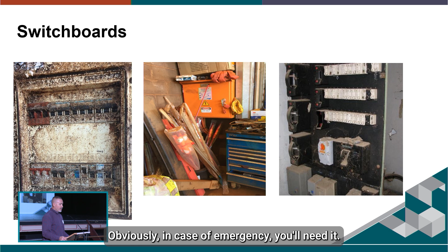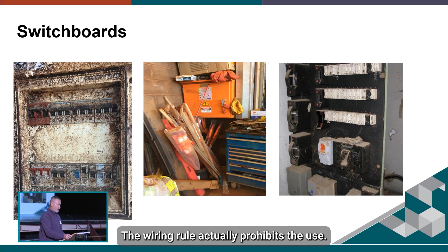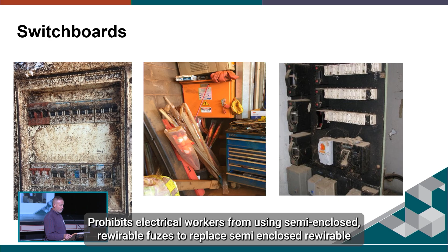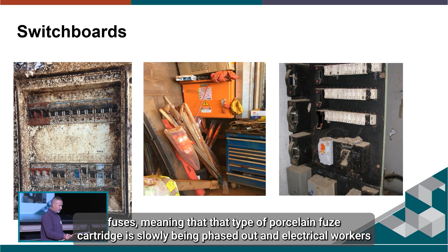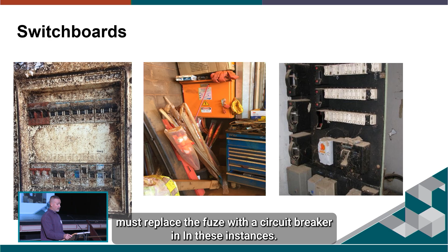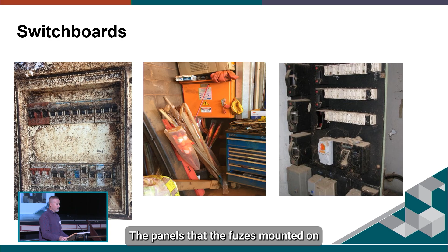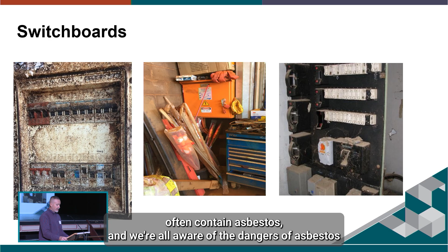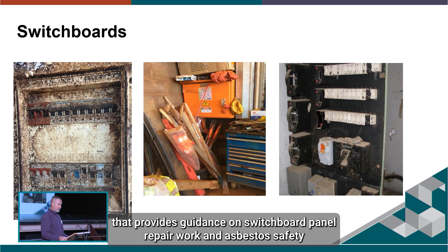On the right-hand side there, you'll see an older type of meter panel, switchboard box with the black background. The wiring rule actually prohibits electrical workers from using semi-enclosed rewirable fuses to replace semi-enclosed rewirable fuses, meaning that type of porcelain fuse cartridge is slowly being phased out, and electrical workers must replace the fuse with a circuit breaker in these instances. The panels that the fuses are mounted on are often asbestos, and we're all aware of the dangers of asbestos. Building and Energy have published a fact sheet that provides guidance on switchboard panel repair work and asbestos safety.